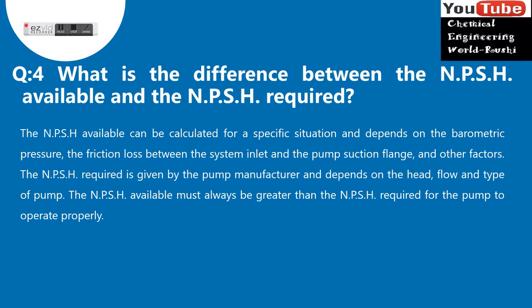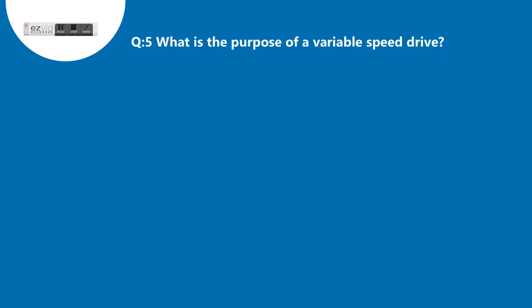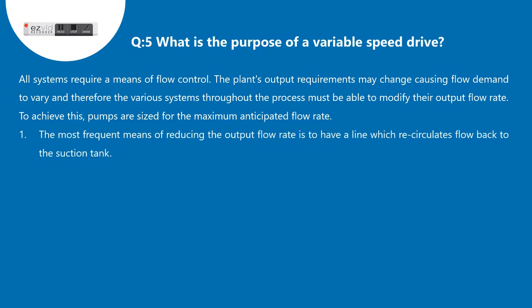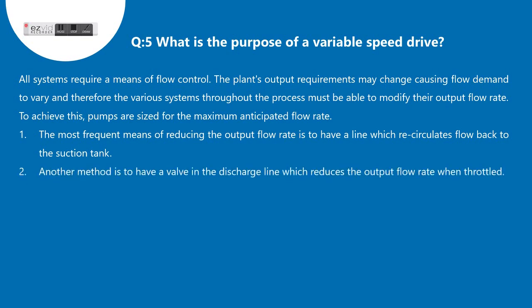Question 5: What is the purpose of a variable speed drive? All systems require a means of flow control. The plant's output requirements may change, causing flow demand to vary, and therefore the various systems throughout the process must be able to modify their output flow rate. To achieve this, pumps are sized for the maximum anticipated flow rate. The most frequent means of reducing the output flow rate is to have a line which recirculates flow back to the suction tank.